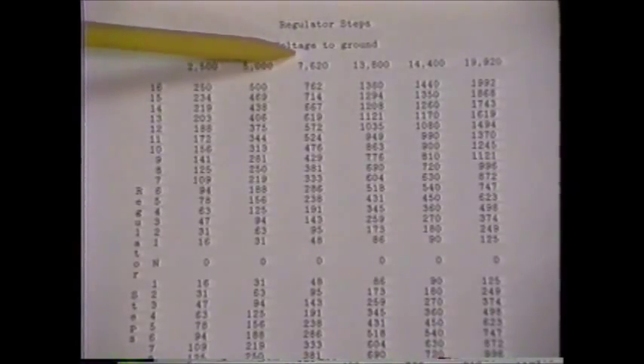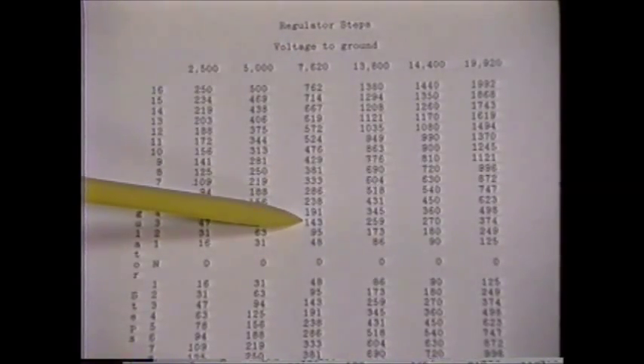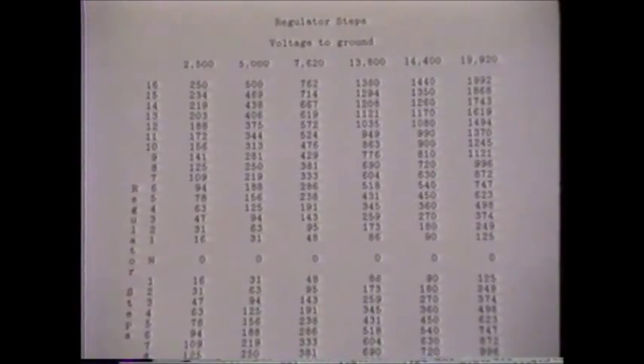From the third column in the chart, we see that the initial reading of 150 volts for a 7,620 volt regulator would most closely match the voltage of 143 in the chart, which correlates to the third step. There is approximately 48 volts per step for this size regulator. The regulator we're testing is indicating 150 volts. If this is in fact the third step, we are measuring 50 volts per step on our regulator.